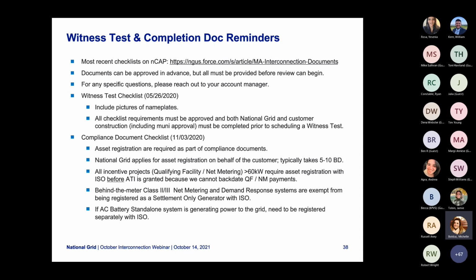Reminders specifically around compliance documents. Asset registration is part of compliance documents. National Grid will register the assets on behalf of the customer, which can take typically 5 to 10 business days. Because we cannot backdate payments, incentive projects greater than 60 kW require asset registration with ISO before ATI can be granted. Behind the meter class 2 and 3, net metering and demand response systems are exempt from being registered as settlement-only generators with ISO. If an AC battery standalone system is generating power to the grid, it also needs to be registered separately with ISO.